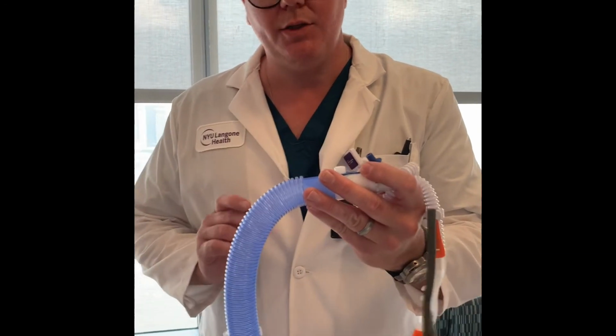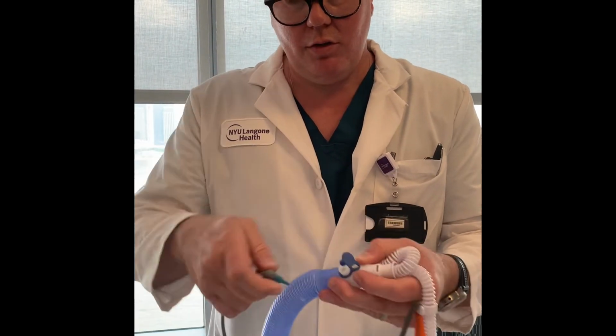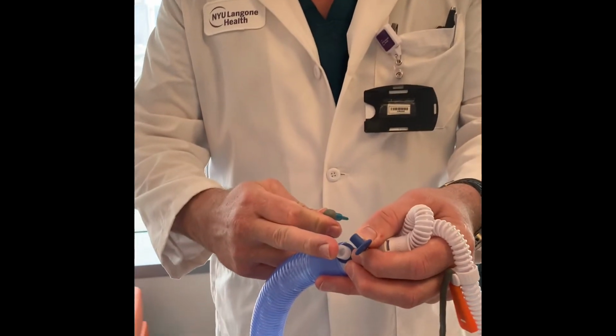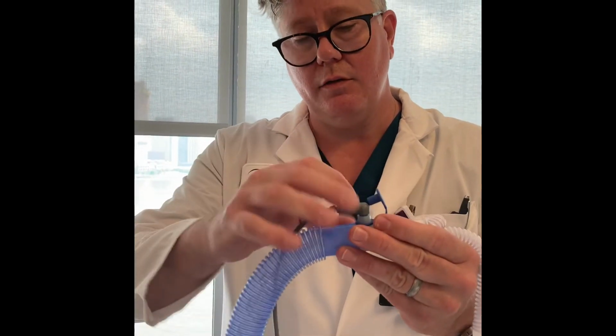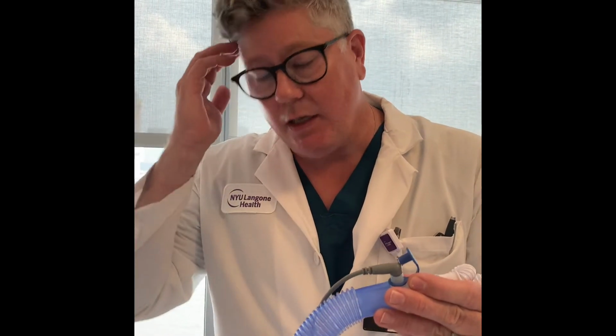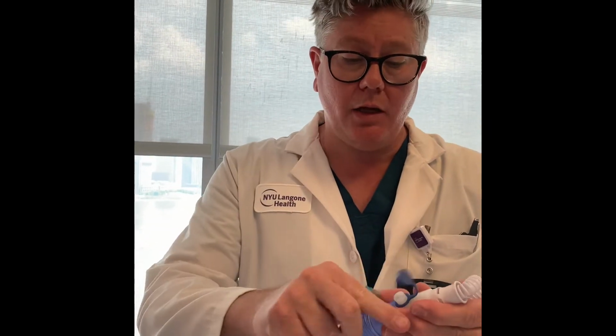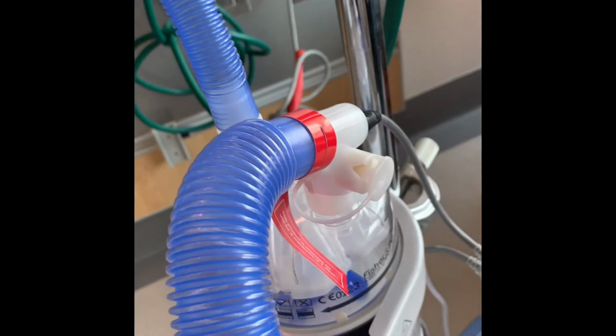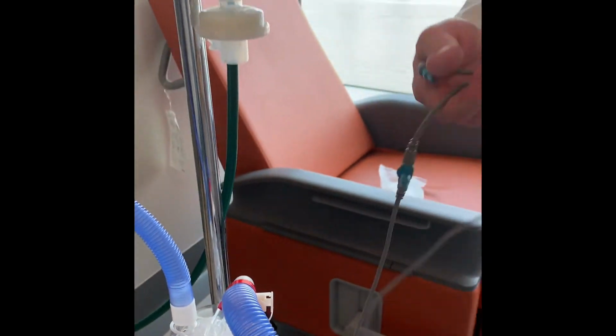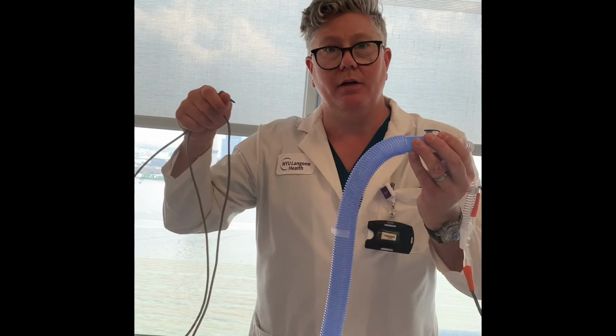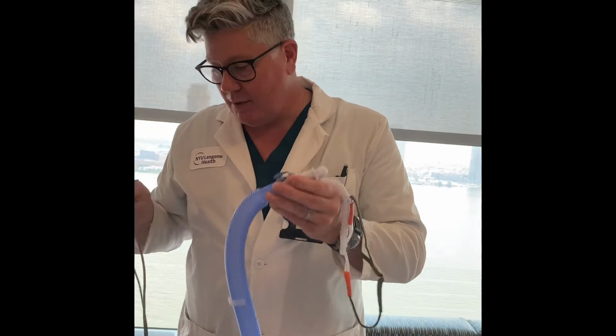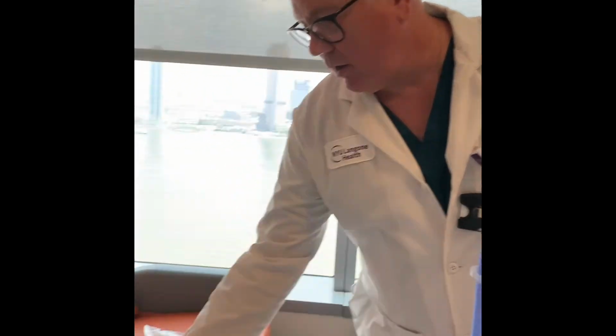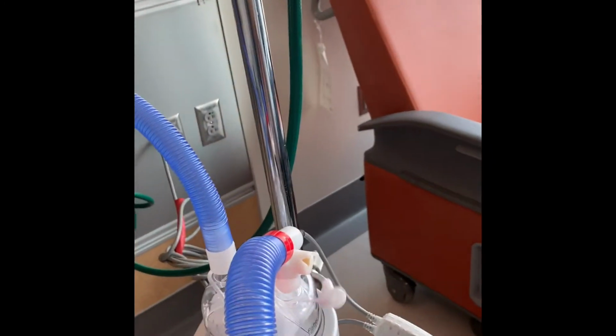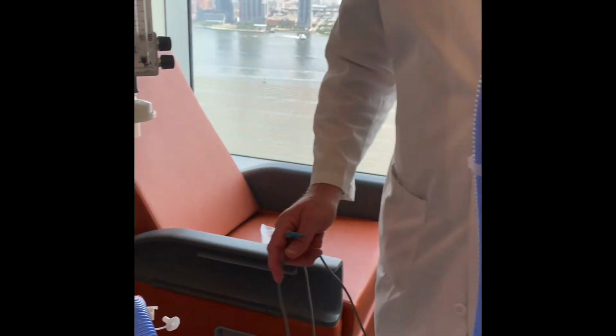So just be aware, please, that if this were to pop out, you're going to have air coming out of here. So make sure that the end of the heated wire is always in there. If you're having trouble finding a heated wire, you can close this port, and you can close this port here, and you can deliver the high flow. It's just not going to have heated humidity until we find one of the heated wires. It's an option if you can't find them. Okay, but these are different spots where there might be a disconnect, and then the patient's not getting all the flow they need. You'll hear it, it'll be a pretty loud sound.